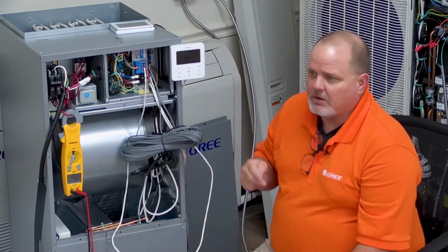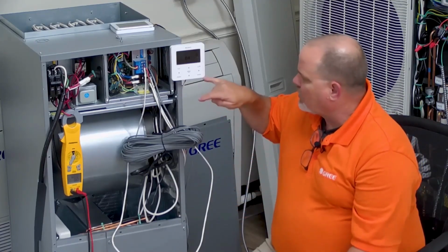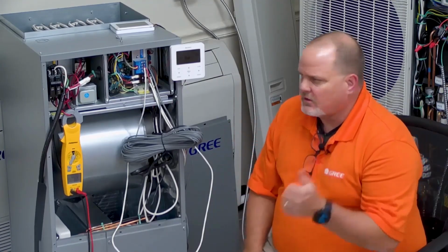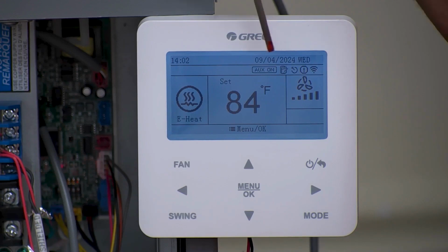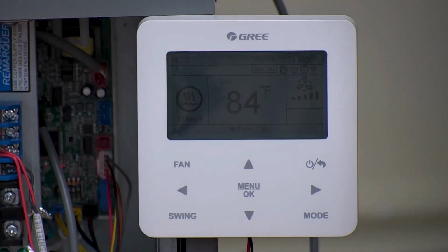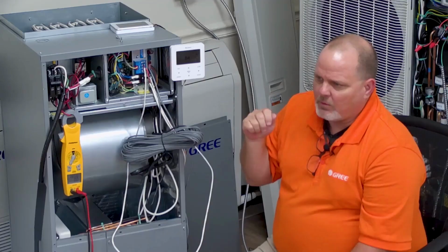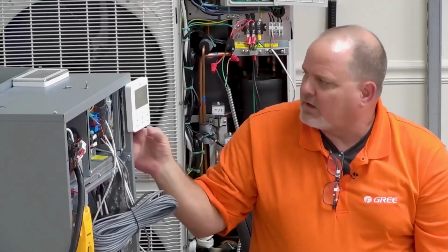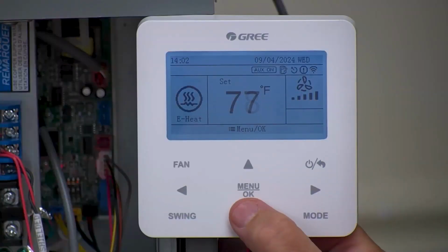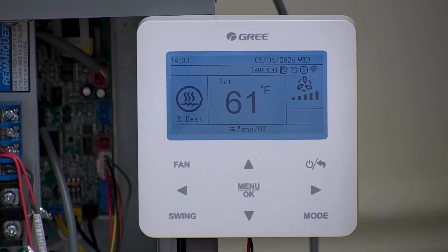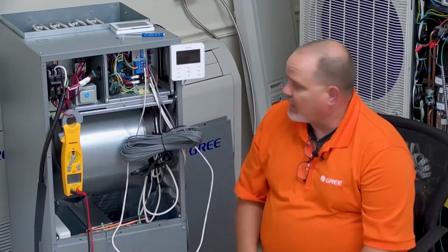And then the other mode you have is E-heat mode. If for some reason you're out on error code or anything like that, you can go to your mode settings, change it to E-heat, set the temperature, and you're good to go. There we go. She's on. As I said, it shows auxiliary on. So I didn't time that, but I would say it's probably close to 5 minutes. It's got to be at least 5 minutes off, because as you've seen when I first did it, electric heat came on right away. But once you cycle it off and it cycles back on, it's going to have a 5-minute delay. So now I'll run this back down. We should be able to lose our auxiliary heat call. So we lost it. We also lost the amp draw. So whatever the blower time delay off is, which I'm not even sure how long that is, it did slow down a little bit. And then that'll cycle off.